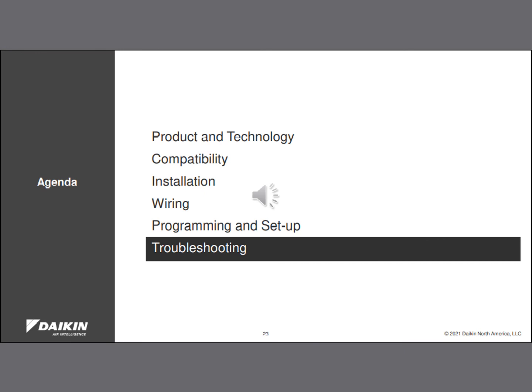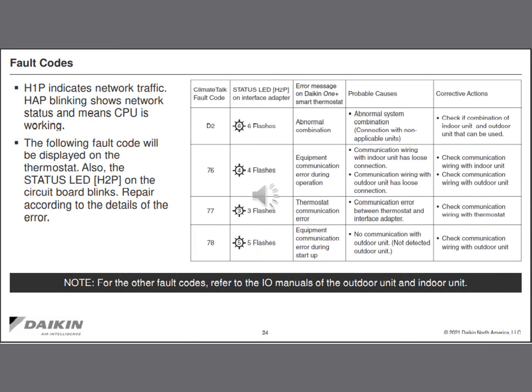And once you have your cool settings in place, you can go ahead and follow up with your commissioning of the system. You can complete the test mode just like you normally would on any Daikin FIT system. You can also roll the system into charge mode, where you can verify the charge via the subcooling method, and round out the commissioning and set points of the system. Very straightforward. Now we'll touch on just a few troubleshooting items that are available with this adapter.